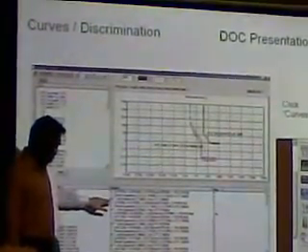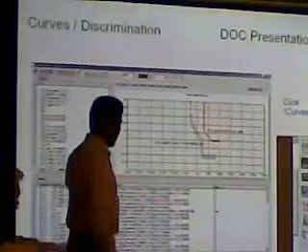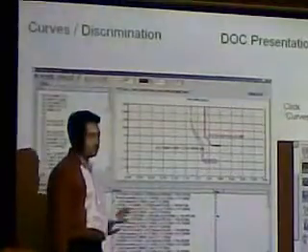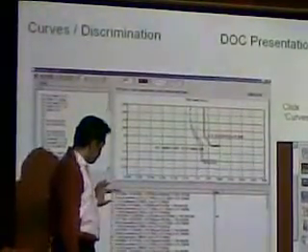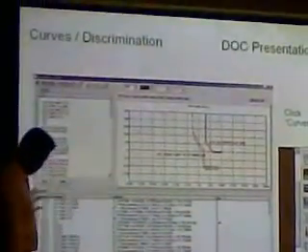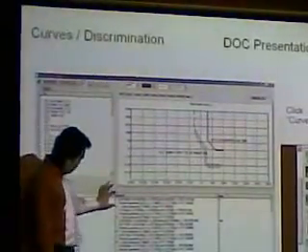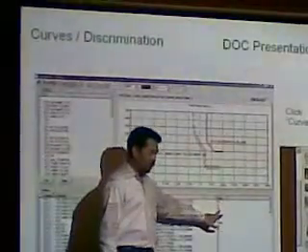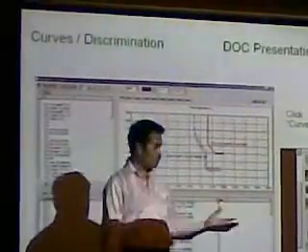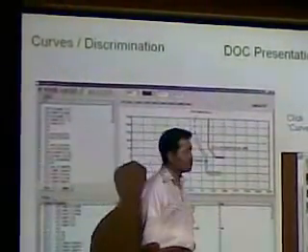And then short circuit protection, and then indirect contact protection, that means earth fault. That is IEC terminology, indirect contact, that is earth fault. So it ensures the 3 protections based on this breaker and this cable, upstream and downstream. These 3 protections are okay. But when you don't achieve the protections, you will see a fail.